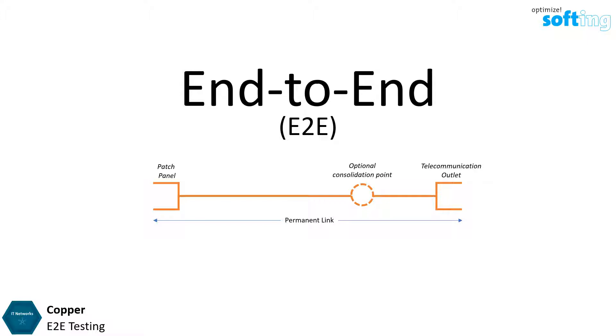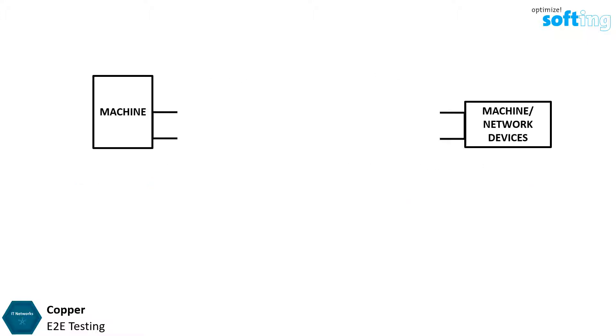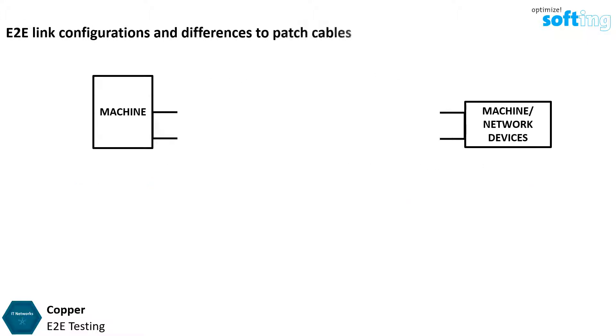A channel is the complete horizontal cabling path including the permanent link, and any cross-connects and/or patch cords attached to both sides of the link. In an industrial environment, where machines are directly connected to machines or network devices such as switches without using additional patch cords, an end-to-end link is used for these applications.